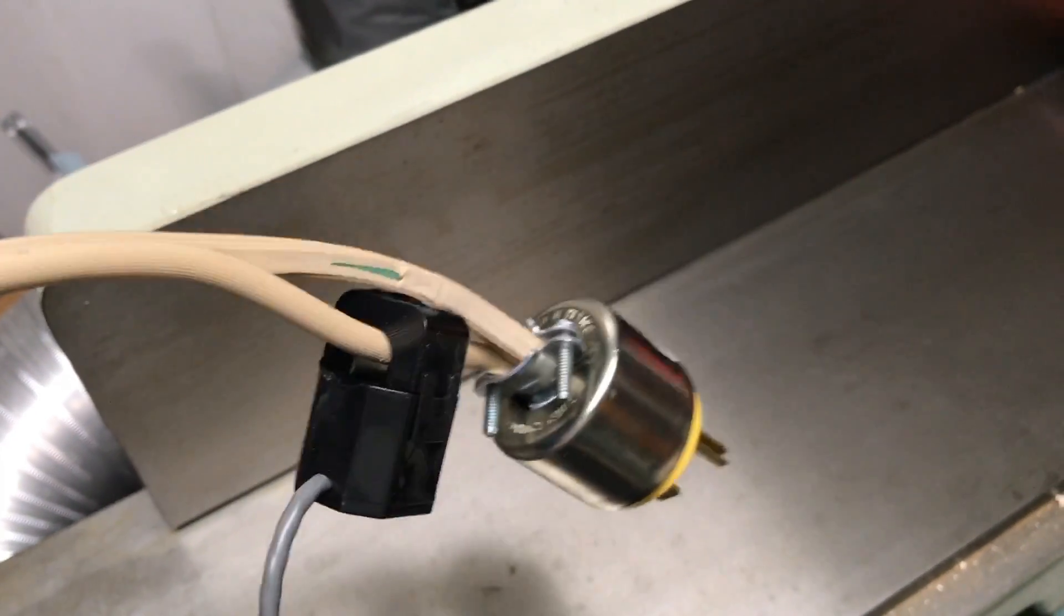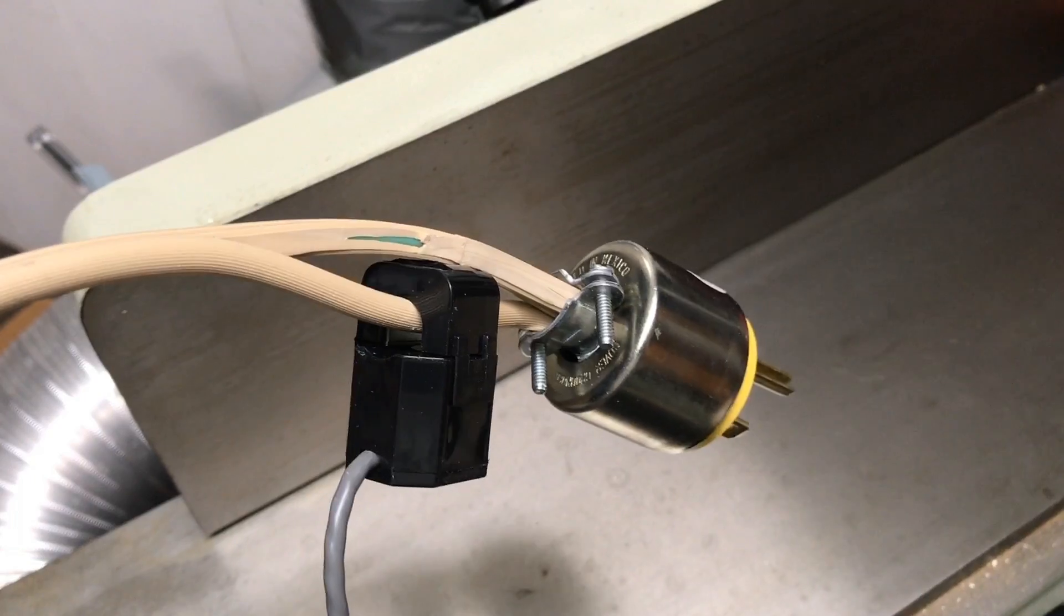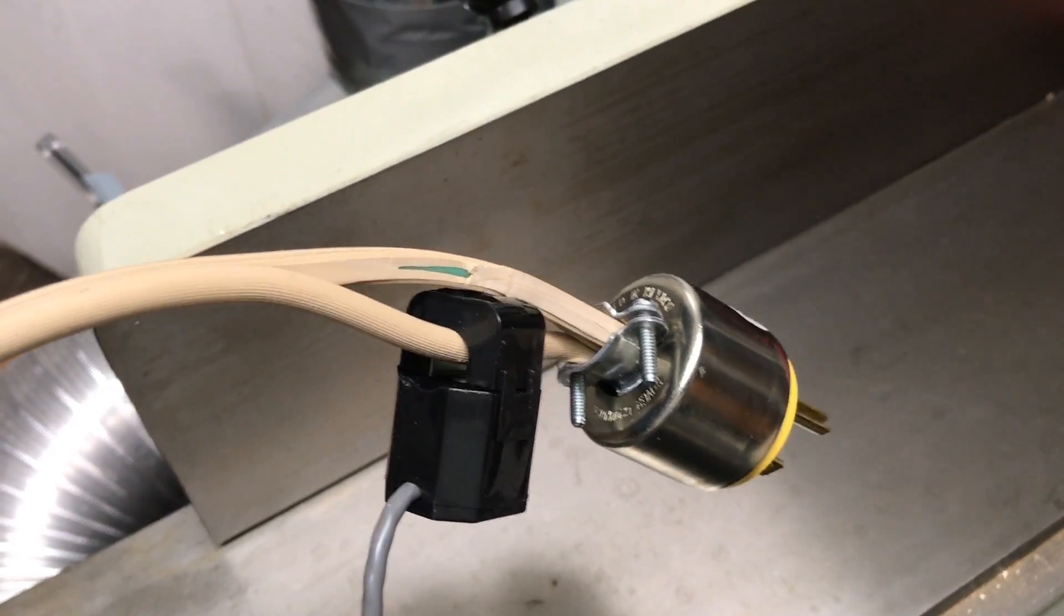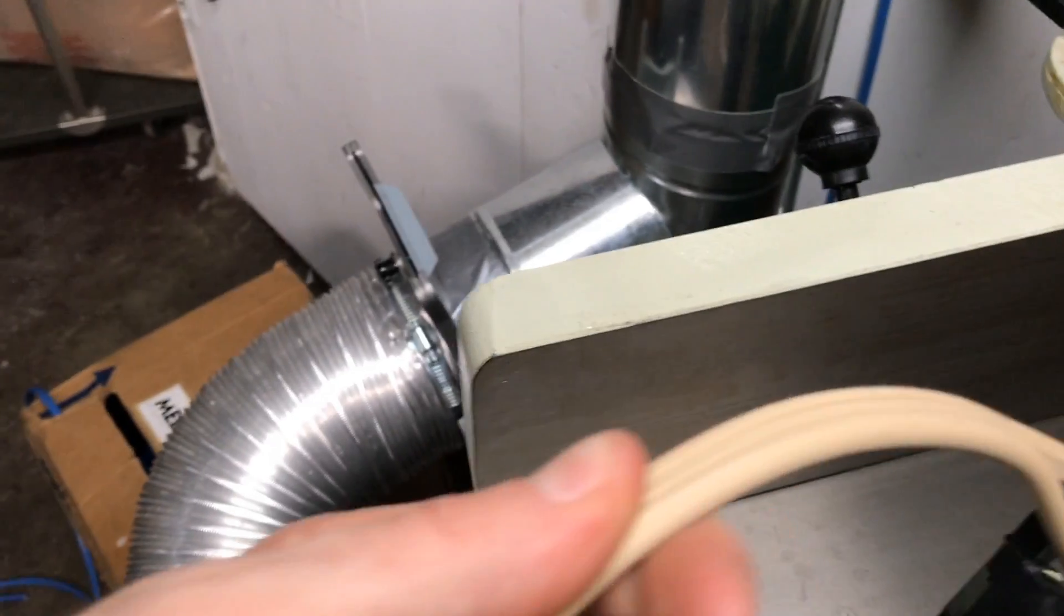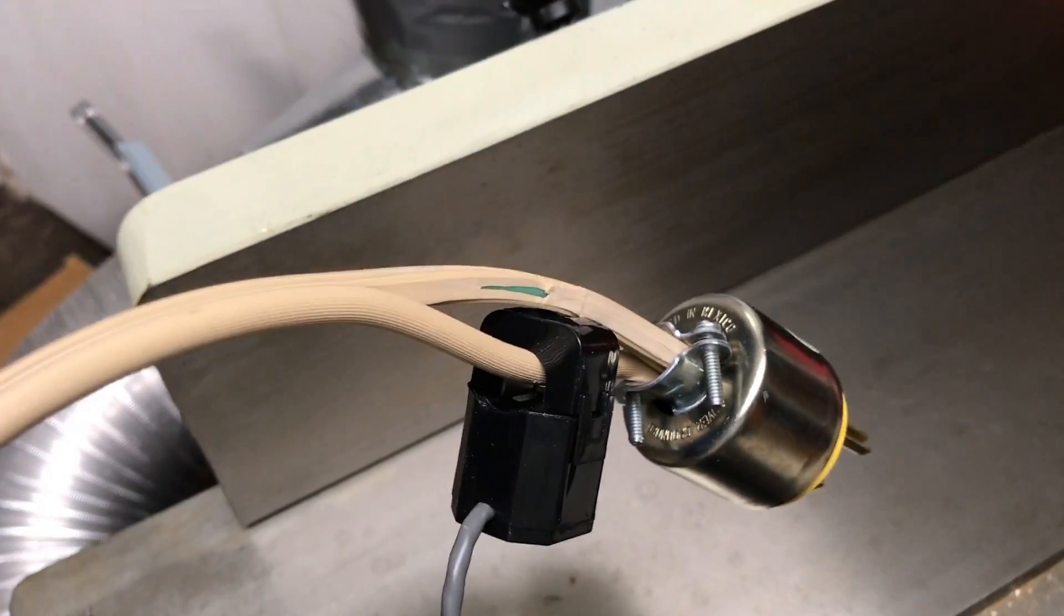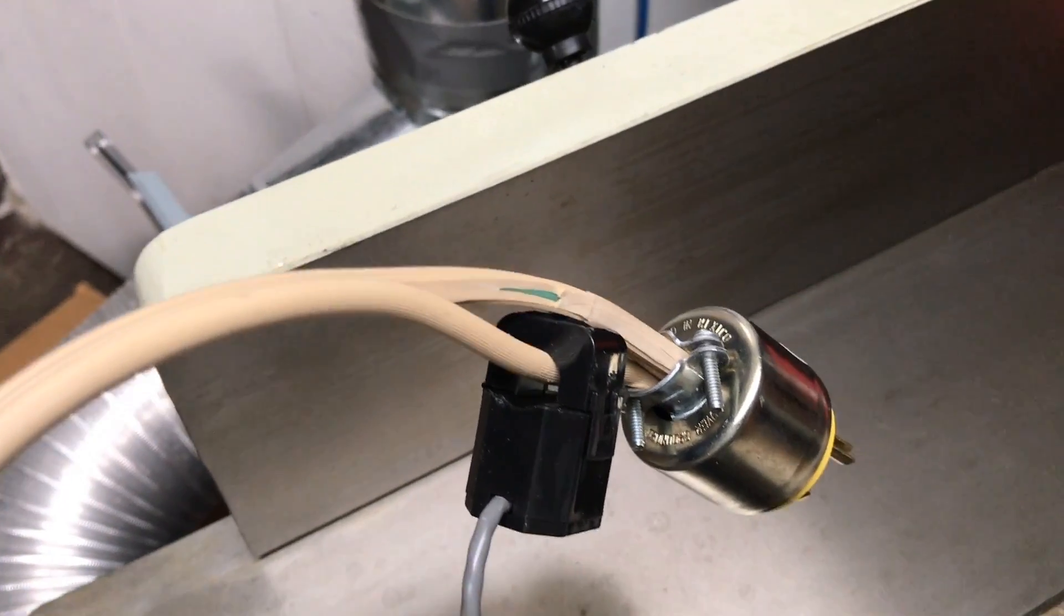The key about the current sensing transformer is it will sense however much current is passing through it. However, it can only be around one of the leads because it senses the sum of all the current going through it. If you were to just clip it around this entire wire, you would end up getting zero because the current flows in one side in the neutral or in the hot and then out the neutral.